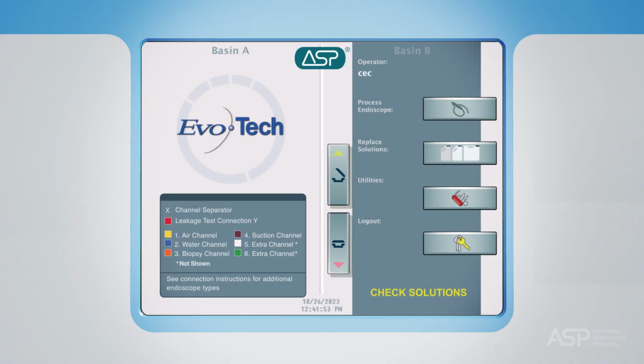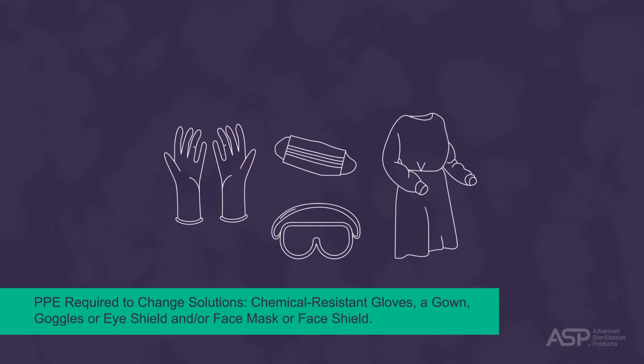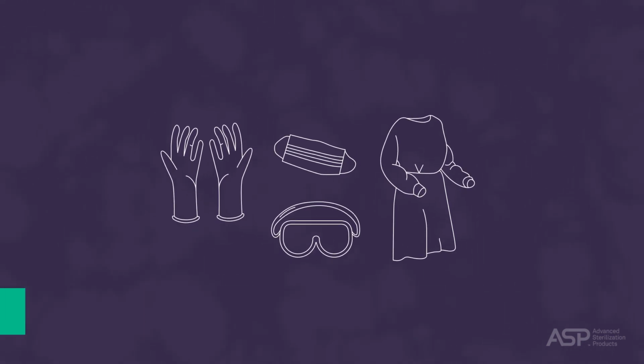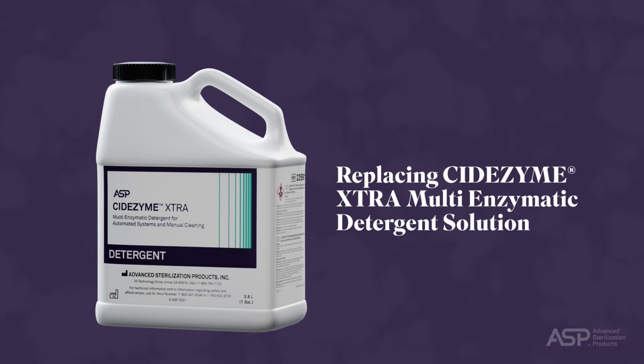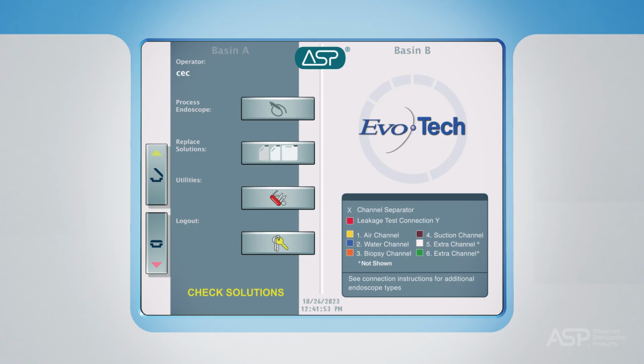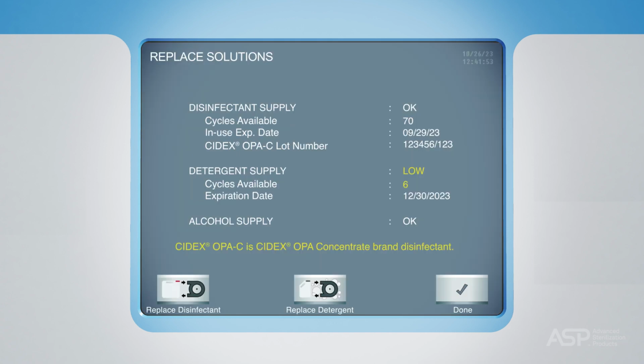The system will indicate on the screen when any of the chemicals are low or empty with a yellow warning. A red screen indicates that a bottle is empty and will no longer run a cycle until the EVOTECH ECR solutions have been replaced. PPE is required and both basins must be idle to change solutions. To replace CIDEZYME XTRA Multi Enzymatic Detergent Solution, touch the button on the display screen that shows 3 bottles and states Replace Solutions. At the bottom of the screen, select the button Replace Detergent.